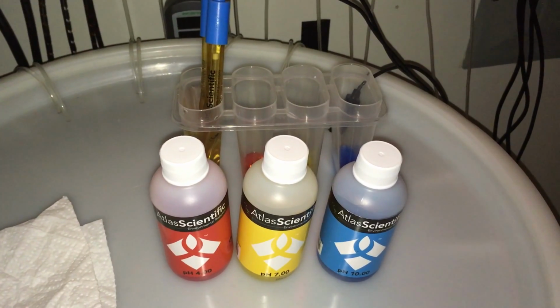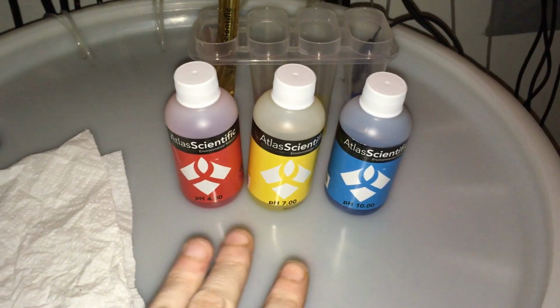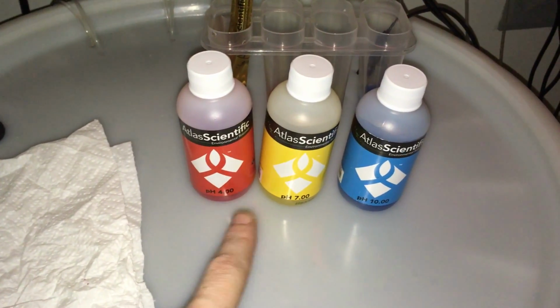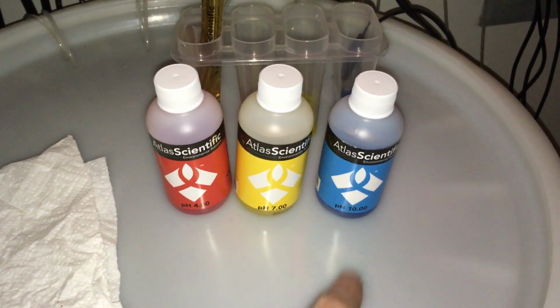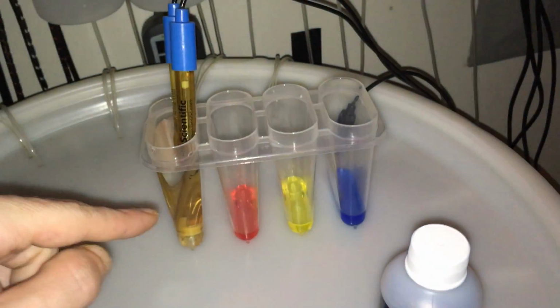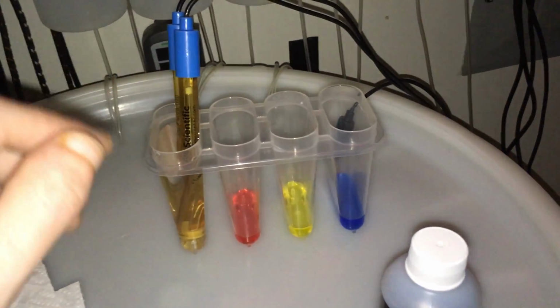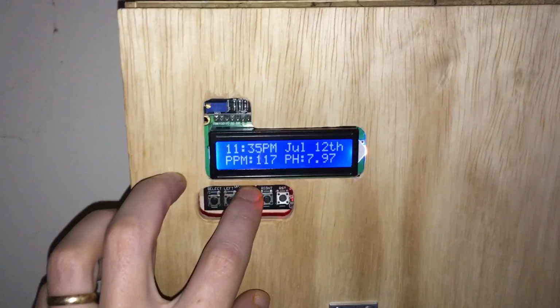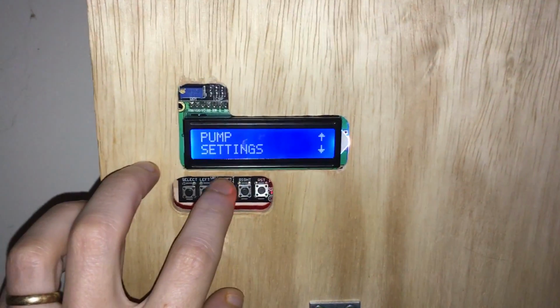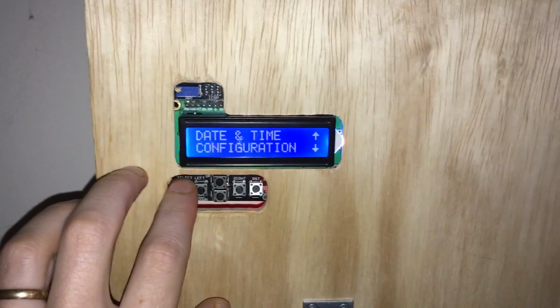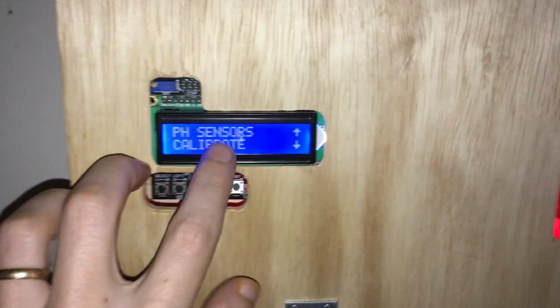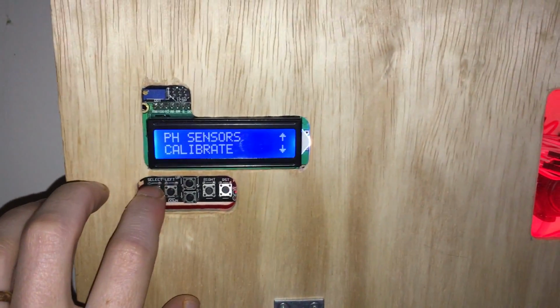Now let's talk about our pH probe calibration. So we have a 3-point calibration again. It's going to be 4.0, 7.0, and 10.0. And using the same popsicle mold, I've gone ahead and filled up the first chamber with fresh water that we're going to use to clean the probes off as we dip into each solution.